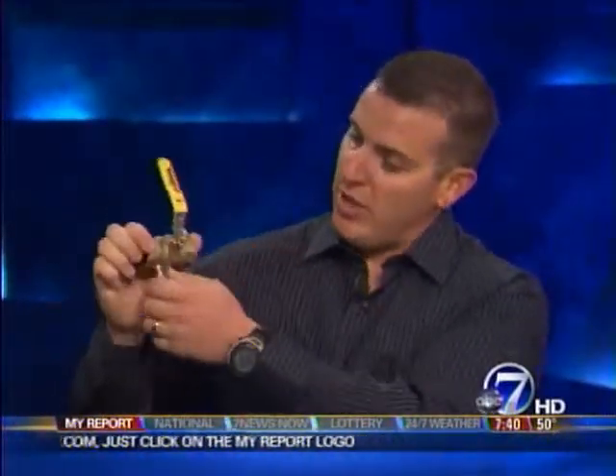So what do we need to do to take care of this? I have a short three-step plan to protect it in case of freeze damage. First, go downstairs to your basement or crawl space, turn your valve perpendicular to your standpipe, and make sure the sprinkler water is shut off. Then quickly drain the little bit of water out of the copper pipe down there in the basement.